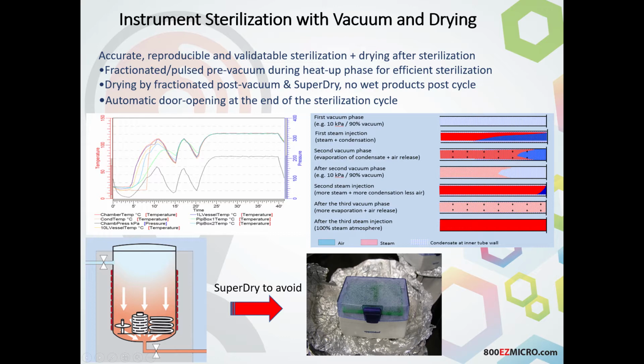Liquid is its own sterilizing agent, so we only need it to achieve 121. We're not as interested in steam penetration at that point because we are actually just achieving 121 for that. However, steam penetration is the absolute most important thing with instrument or waste sterilization. So in the diagram that you would see on the right, the different colors represent tubes.